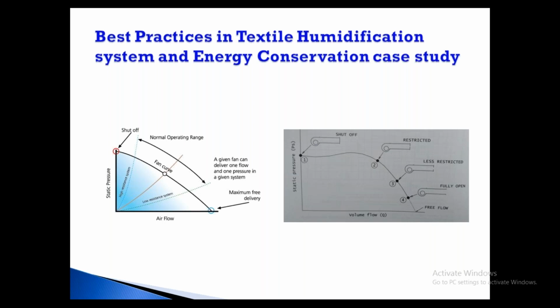So once you have found the total pressure and the volume of the air, then you can collect the reading from the motor: what RYB current the motor is taking, with the voltage and power factor. You will know the kilowatts it is taking. So for that particular kilowatt power, how much air it is delivering at what pressure. Based on that, you know the Q, and you can find out the efficiency of the fan. But that is the practical point I am telling, the efficiency of the fan, but that is not the correct efficiency.